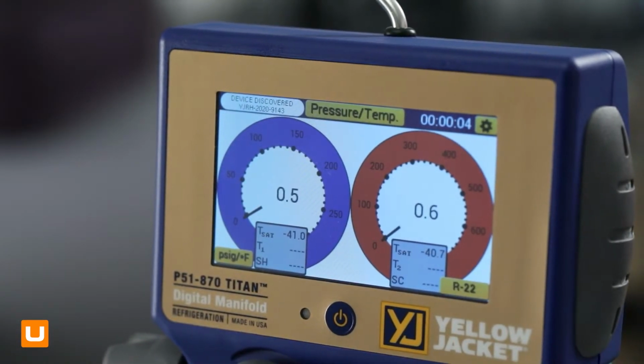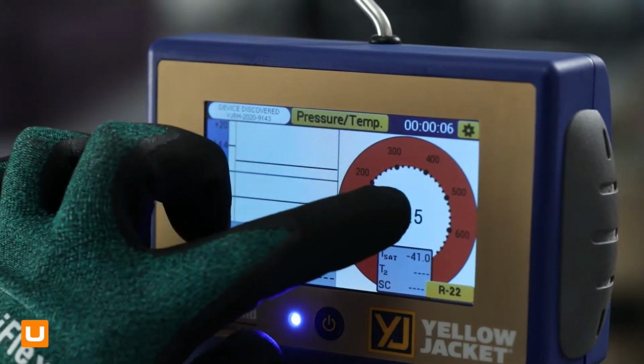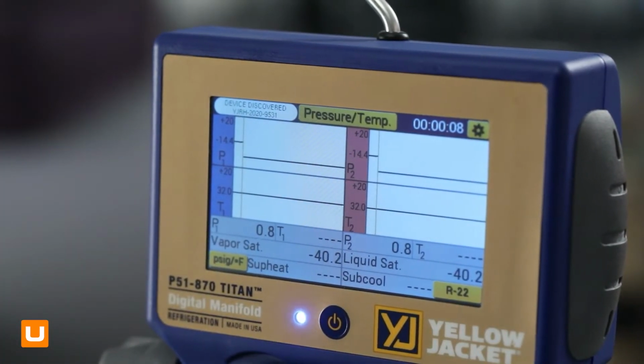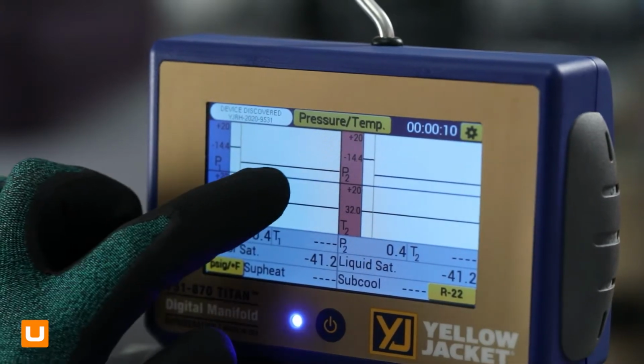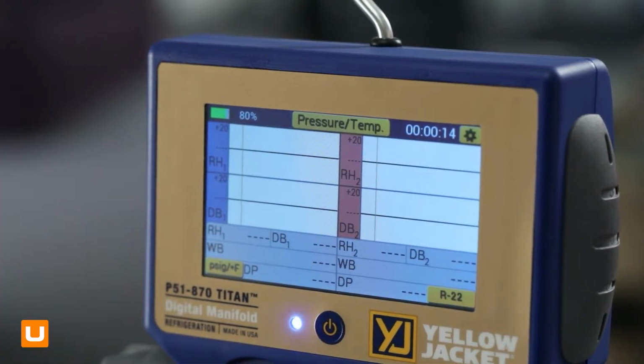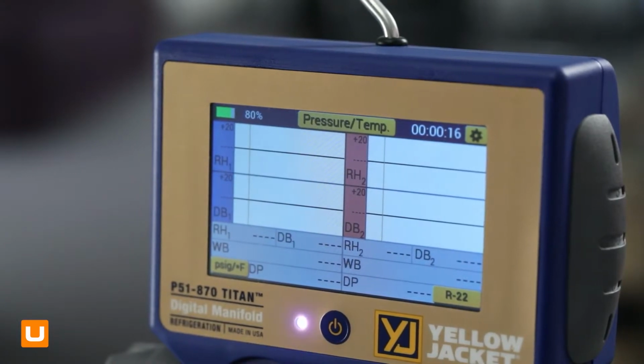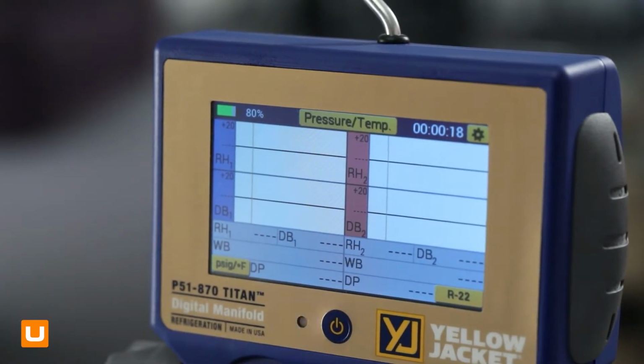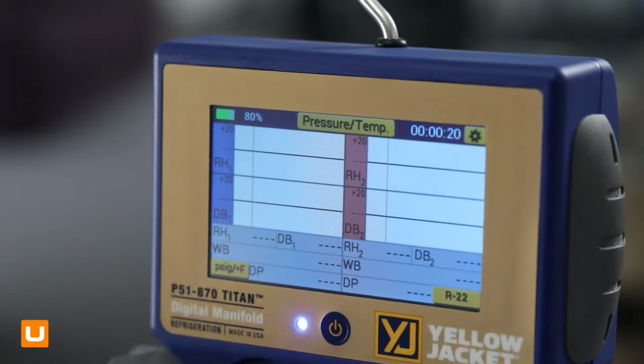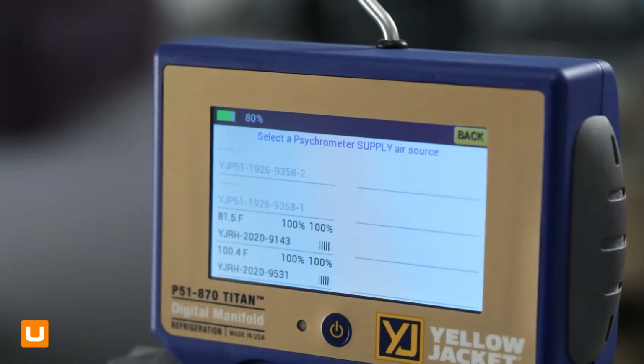But by tapping in the middle of the gauges, the app first brings up the pressure temperature line graphs. Tapping a second time changes the display to the psychrometric readings screen. To assign the psychrometer probes, tap on the gray box below the blue supply side graphs.